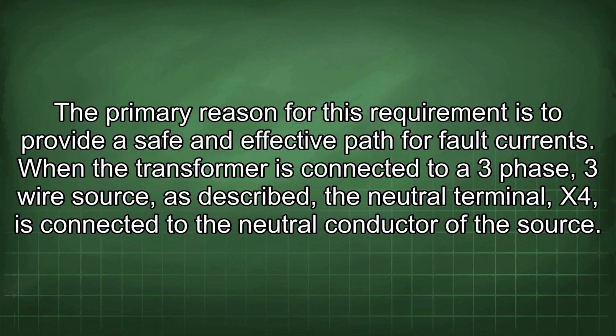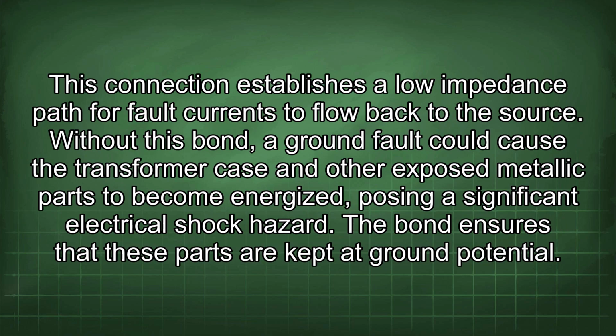The primary reason for this requirement is to provide a safe and effective path for fault currents. When the transformer is connected to a 3-phase, 3-wire source, as described, the neutral terminal, X4, is connected to the neutral conductor of the source. This connection establishes a low impedance path for fault currents to flow back to the source. Without this bond, a ground fault could cause the transformer case and other exposed metallic parts to become energized, posing a significant electrical shock hazard. The bond ensures that these parts are kept at ground potential.